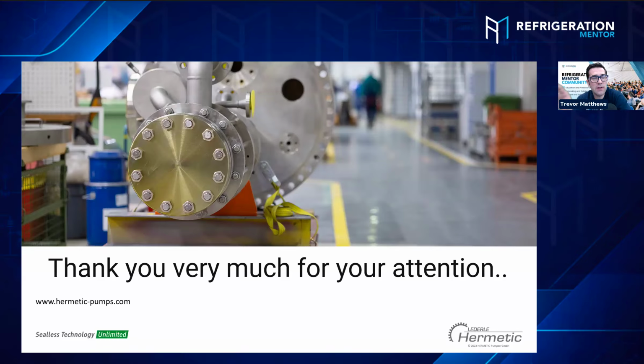Okay, great. So now a system has been running for a long time, and you've got the maintenance team in there as technicians. What are some of the critical maintenance items to check in these pumps? Like flashing, which we talked about. If you start hearing noise, that's something you want to look at. I guess matching it up to the amps, checking your differential, and the filter you mentioned, checking the pressure differential across the inlet filter. Are there any other maintenance items they should check?